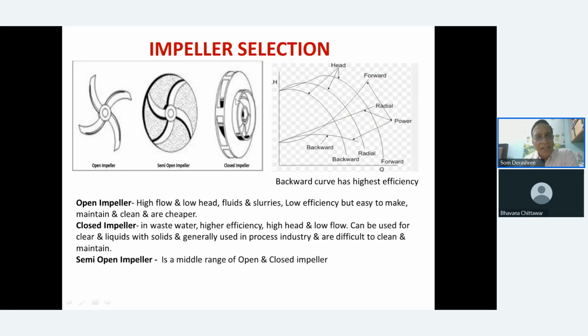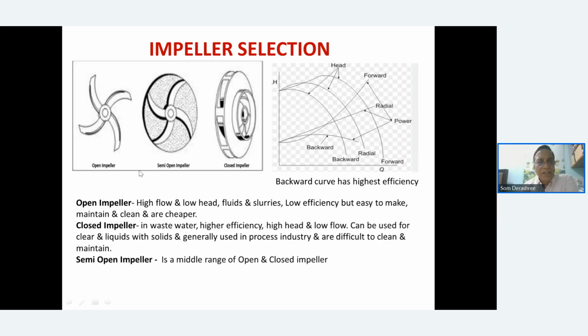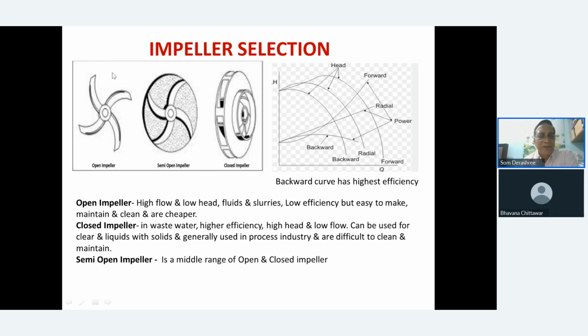Then you have impellers. Now you have three types of impellers, basically. Open impellers give you very high flow but very low head, and are used for fluids and slurries; low efficiency but easy to make and maintain. So this is very cheap actually. This is the semi open impeller, or again you have for wastewater comparatively higher efficiency and high head and low flow. And then this is for the closed impeller. A semi open impeller is somewhere in between. The closed impeller gives you much higher efficiency; you can have wastewaters or higher. High head and low flow, and can be used for clear liquid, and generally used in the process industry. You will find most of the process industries using this.